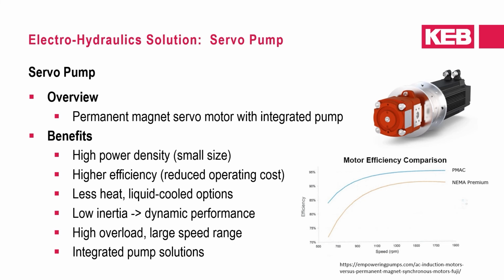On the other hand, synchronous permanent magnet motors, otherwise known as servo motors, have been gaining ever-increasing prominence, and for good reason too. Compared with an induction motor, they have very high power density, meaning more power in a smaller package. They are more efficient, especially under partial loads, thus reducing power consumption and operating costs, and they produce less heat. Also, the rotors are low inertia, which allows fast ramp-up to speed response from idle, and better dynamic speed control performance in response to load steps. And the motors generally have a higher overload capacity and a large speed range.